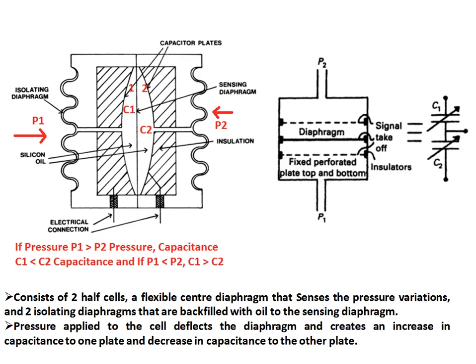When P1 is greater than P2, this pressure causes the sensing diaphragm (the moving plate) to move towards plate 2, causing capacitance C2 to increase compared to capacitance C1. Similarly, if P1 is less than P2, the sensing diaphragm moves towards plate 1, and C1 becomes higher than C2. This vectorial representation is shown in the figure, where C1 and C2 are variable capacitors.